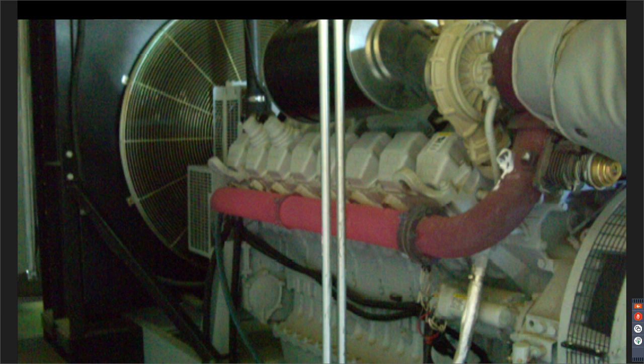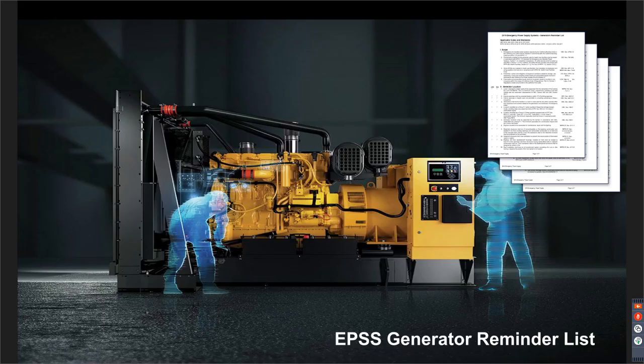So these things run pretty hot. In this particular example, we were doing commissioning of this generator, and the exhaust got so hot it actually ignited the building and caught the building on fire. So things to take into account. There's a very extensive emergency power supply system generator reminder list on the OSHPD website.